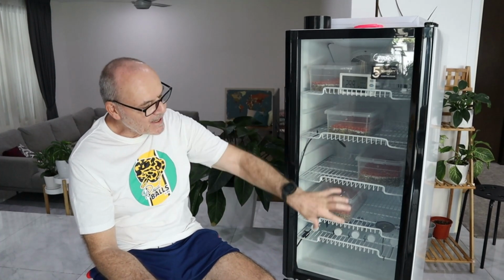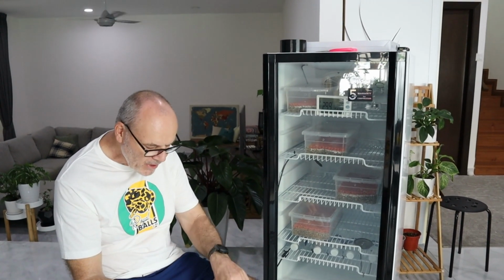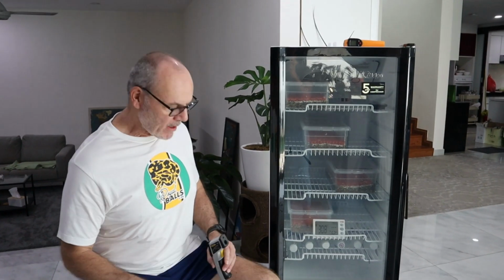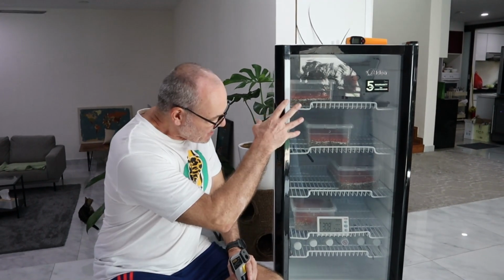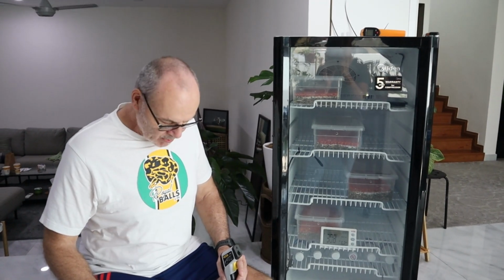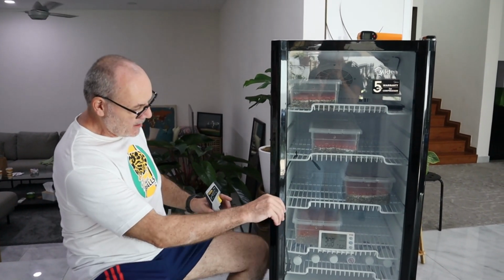So we'll determine first of all what the temperature gradient is in this incubator without a fan. If I get too much stratification, I'll put a fan in. We'll turn the fan on and it will be on permanently for the life of the incubator, and I will readjust my thermostat to get the optimum temperature setting. So we'll come back in about 24 hours and I'll let you know how that goes. Okay, so here we are 24 hours later, and the temperature of the incubator has been just nice for the last 24 hours, which shows that we have enough heat in the system.